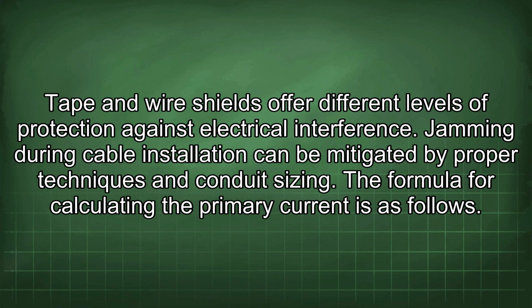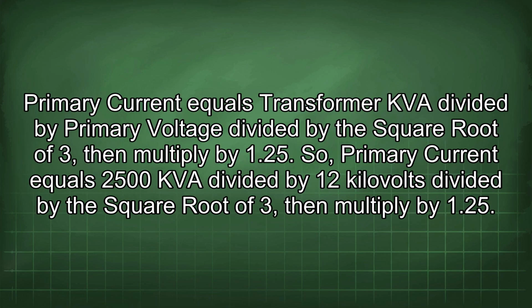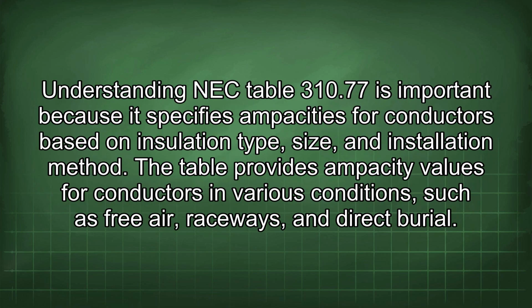The formula for calculating the primary current is as follows. Primary current equals transformer kVA divided by primary voltage divided by the square root of 3, then multiply by 1.25. So, primary current equals 2500 kVA divided by 12 kV divided by the square root of 3, then multiply by 1.25.